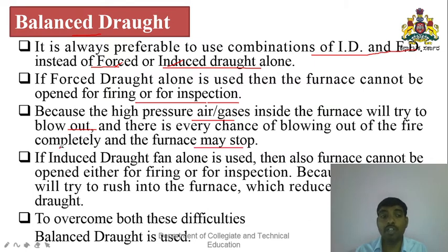That's one drawback. If the induced draft fan alone is used, then also the furnace cannot be opened for firing or inspection, because cold air will try to rush into the furnace, since the air pressure is maintained below atmospheric pressure. When a vacuum is created, there is a possibility of air rushing into the furnace. So induced draft also has a drawback, which reduces the effective draft of the system.